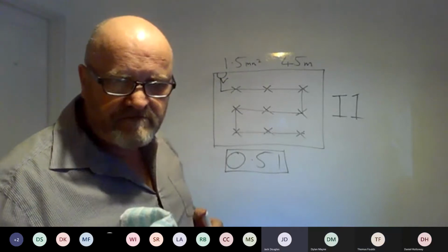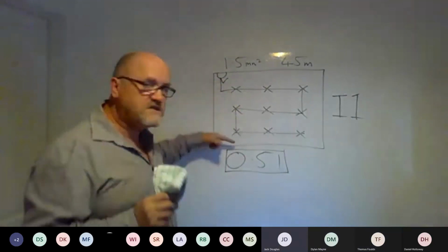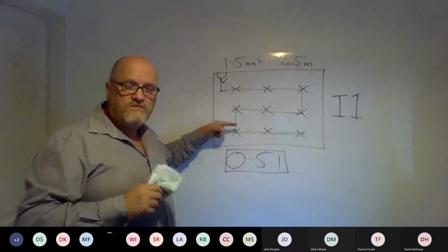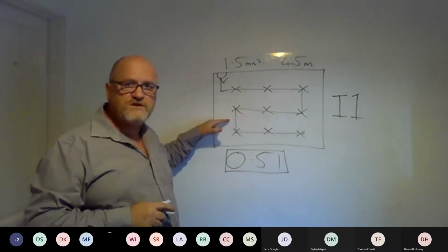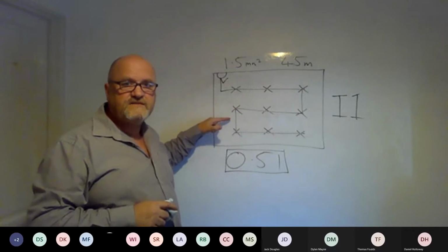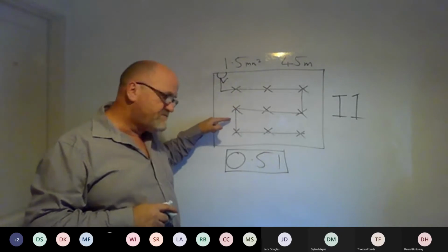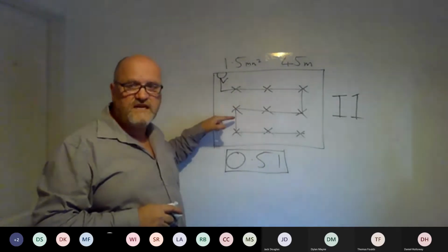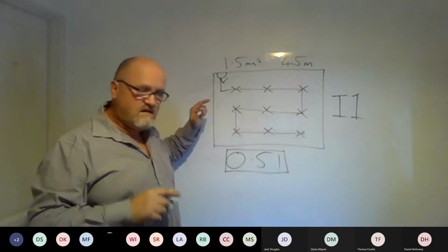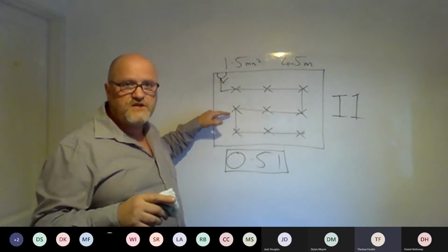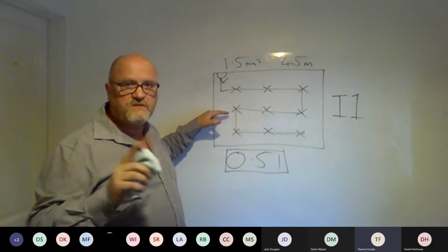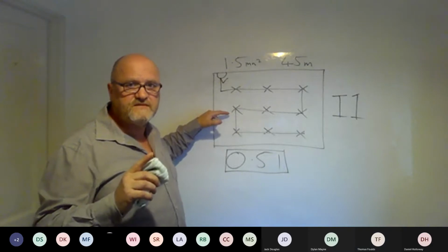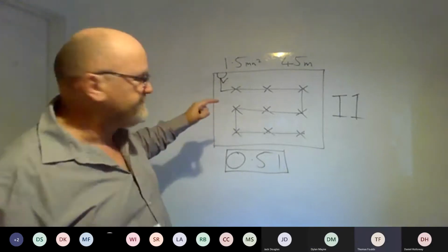Power loss. You get voltage loss in the cables. You'll talk about this later, but the maximum on a power circuit is 5%. I can't lose more than 11.5 volts. And we know we get voltage drop across a load or a resistor. It comes back to that.